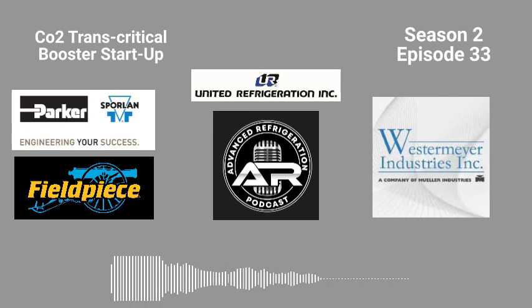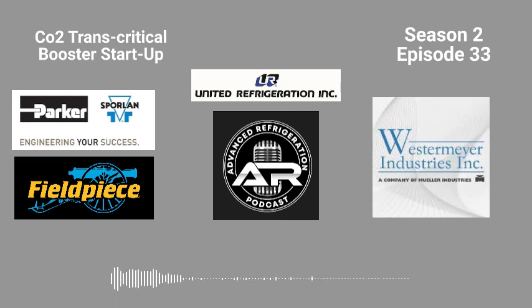No, the iPro was driving the flash gas bypass valve, and then they were using the ESR valve to drive the high pressure valve. Okay. I've done that in a pinch when we burned out a Danfoss 320 or 726 or 7, I think it's a 7, I forget what it is. It's a valve driver board. We ended up burning it out, and then we ended up retrofitting it to an ESR board temporarily. But yeah, that's it.